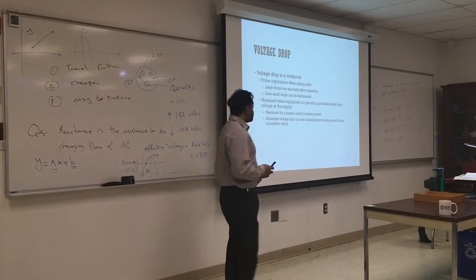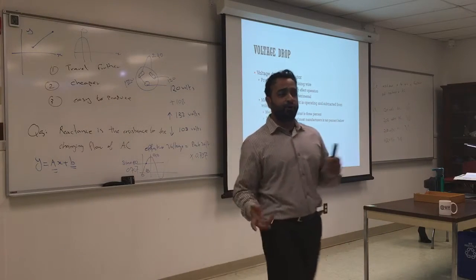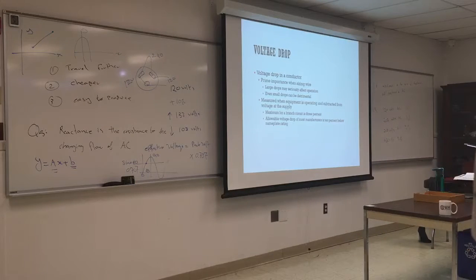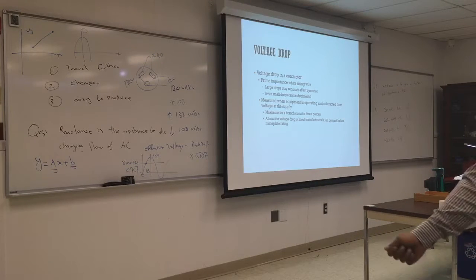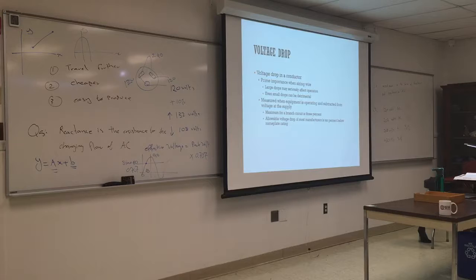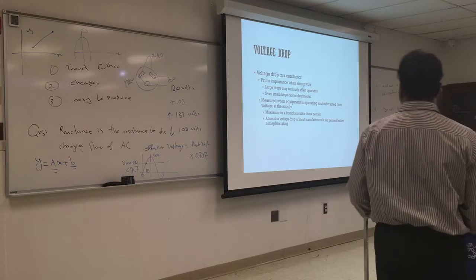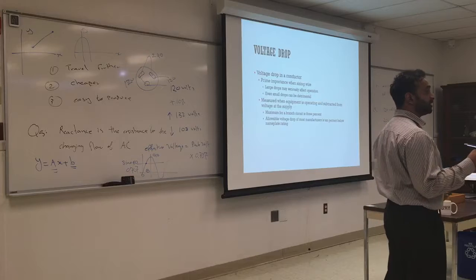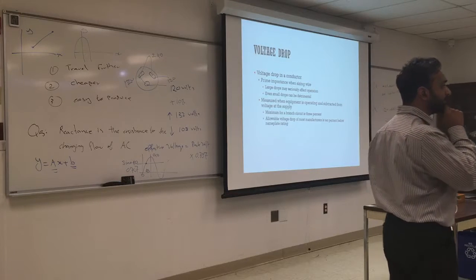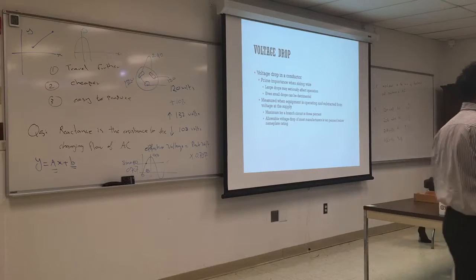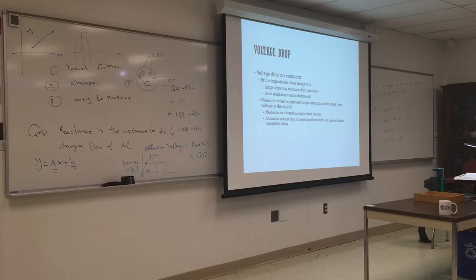So when you do the wiring, before you do the installs, measure the end voltage. So you start with 110 at the receptacle, you go to the end and see how much voltage drop you have. And maybe you messed up something in the installation, or maybe the wire is not connected properly. So look at the voltage coming into the equipment before you do the connection. Question? How do you stop voltage drop then? You can't stop it, you just have to anticipate it. It's going to drop, but I want to know how much it is going to drop.